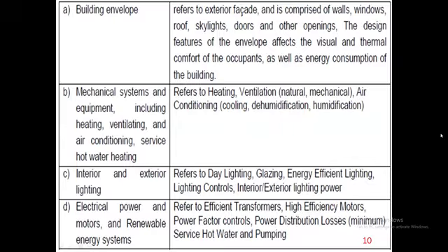And for the motors, any of the motors in India or abroad, I am talking about the 50 hertz cycle only, 400 volts. See, 400 volts for a given motor, supplied at the motor terminals. In any industry, let us say 1000 motors are there, almost 800 or 900 motors are operating at around 70% or 80% only. Very few motors are operating at 100%. And normally the motor is also rated for 380 to 420, meaning around 400 volts for the given motor, it is fine. So these are the areas which we concentrate on in the industries.